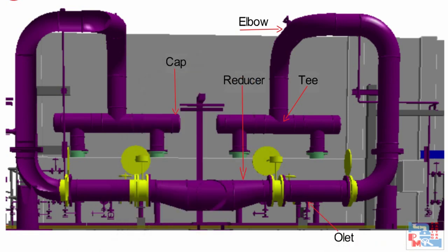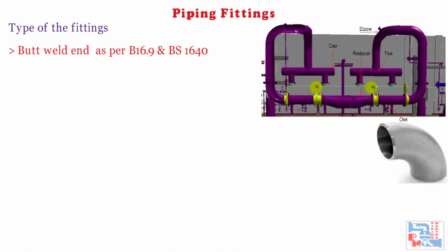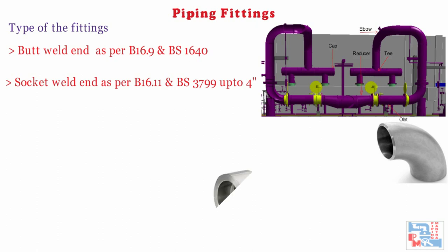In this video, we are going to briefly discuss about end connections. Butt weld end, as per ASME B16.9 and BS1640 — to connect this kind of fitting, the pipe should have a beveled end for welding. Socket weld end, as per ASME B16.11 and BS3799, are available up to 4-inch sizes only. To connect this kind of fitting, the pipe should have a plain end for welding.